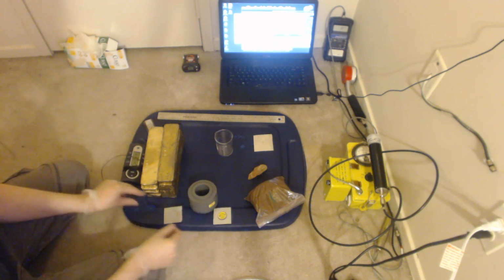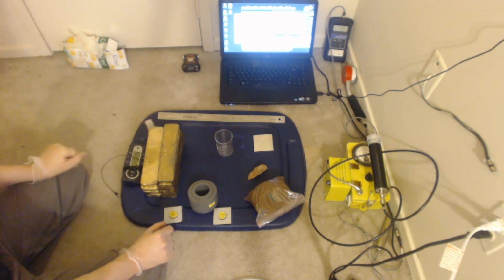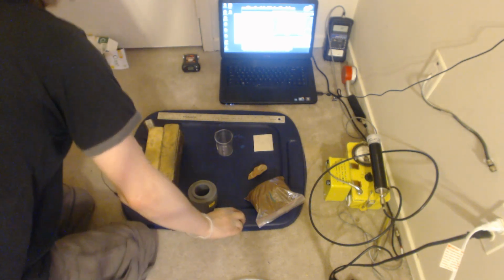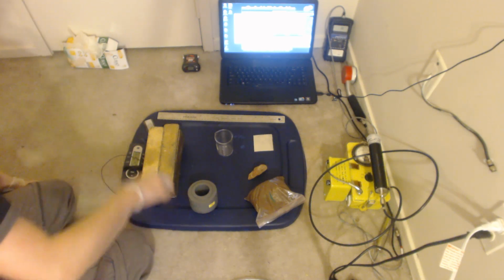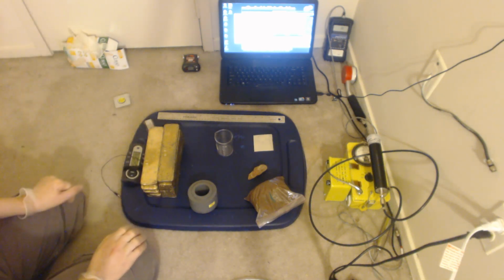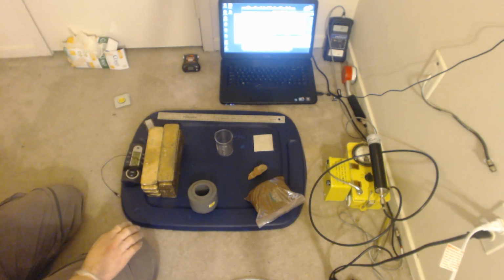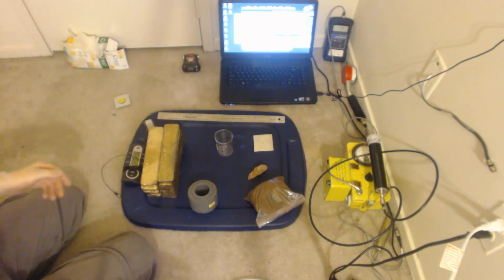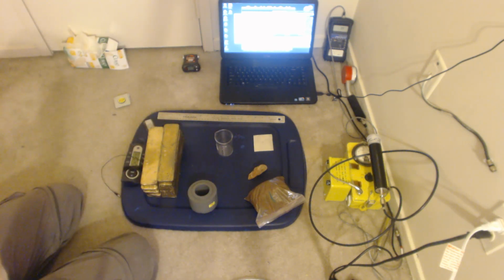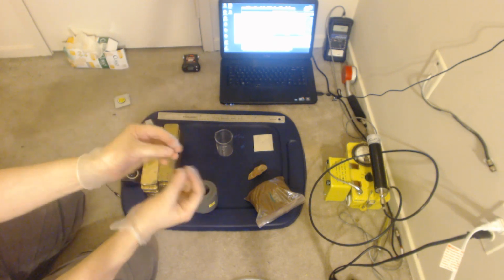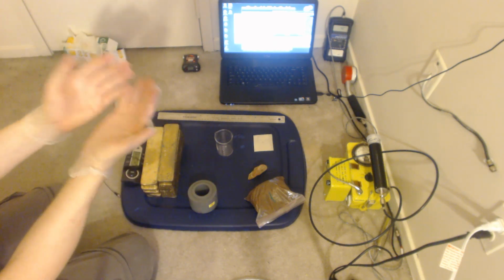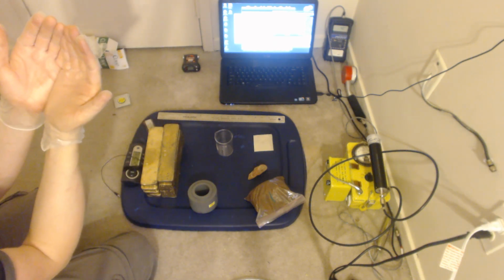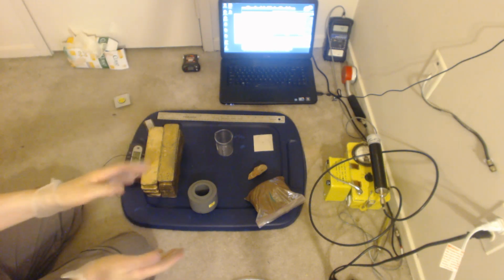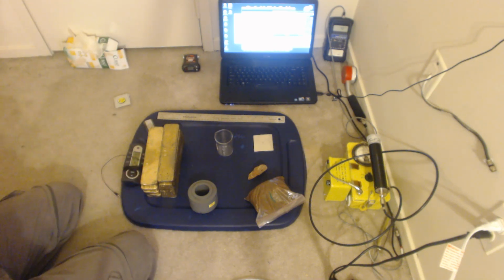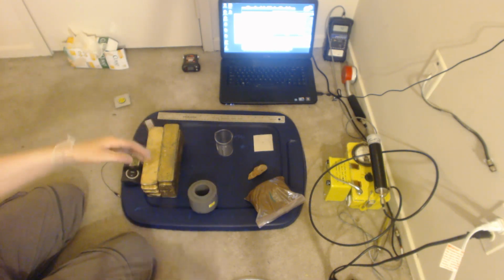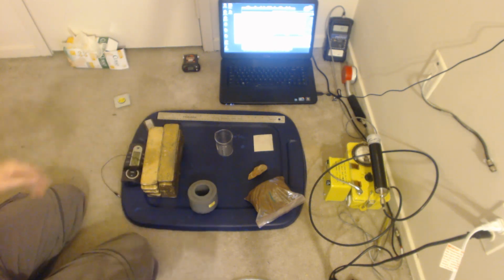All right, so there you go. Let's move these aside, and let's build ourselves a lead castle. Now, scientists call them lead castles. They're the enclosure that encapsulates the probe. Now, my hands could have lead dust on them because I touched lead. I don't see any lead dust. I always clean all my equipment off, so that's perfectly fine. But keep that in mind if you're going to reach over and handle a probe after you touch the lead, that you could be cross-contaminating that.